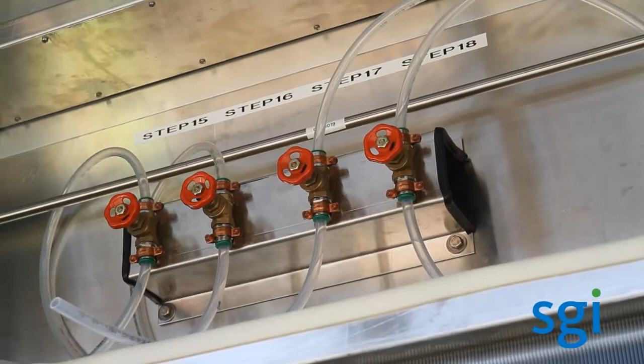So behind the evaporative media section, we have an actual DX coil. In environments where the temperature and humidity are at such a level that evaporative media and outside air and the water that we've talked about isn't able to provide the servers the appropriate inlet temperature or the cold aisle temperature, we offer the customer the ability to add an additional DX coil and/or chilled water coil. The reason we offer both of those is because depending on where you deploy in the world, the customer may have an existing chilled water system.